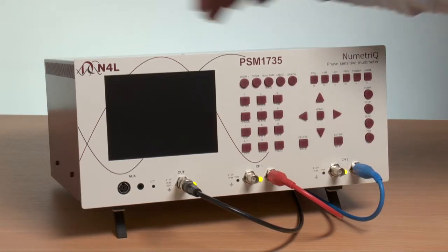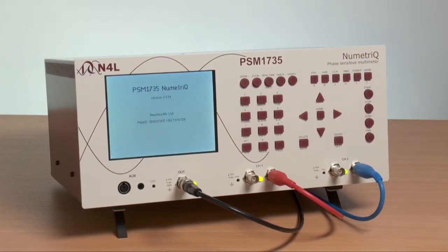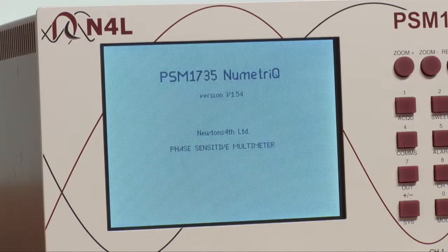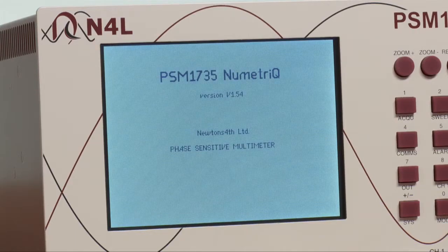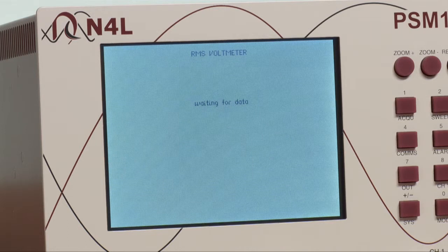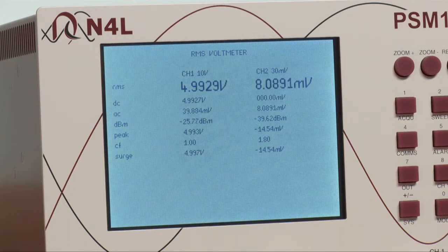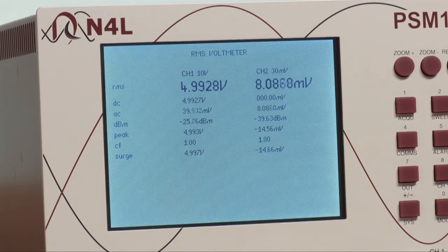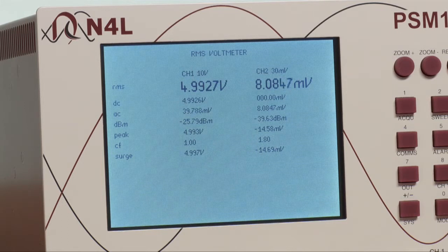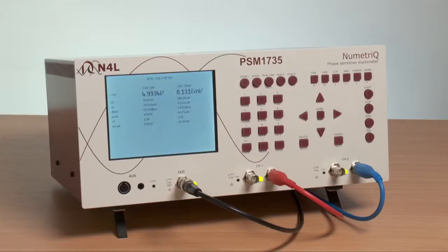If we now switch on the instrument, there will be a power-up routine. Then the default measurement screen will be presented showing RMS voltage measurements on each of the PSM 1735 measurement channels. Here you can see 4.99 volts, which is predominantly the DC voltage on one side of the injection resistor, and 8 millivolts, which is the AC component measured on the other side of the injection resistor.